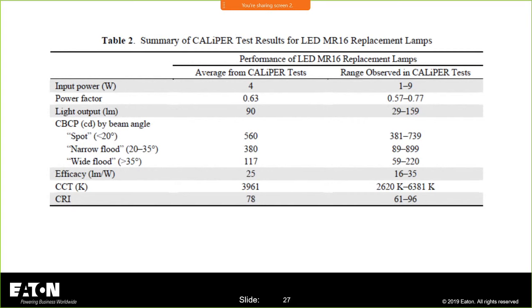And this is a study that was done. I can't remember. I have the link, I think, in the information in where this came from. But there was some research done and testing done where they actually connected LED replacement lamps, and they measured a power factor of 0.63 average, and then the range was anywhere from 0.57 to 0.77 power factor on those floods or on those types of lighting solutions.